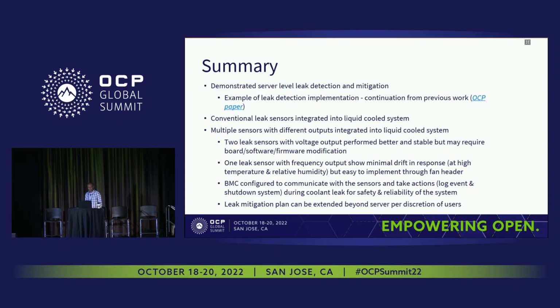To share some of the learnings, the voltage output type sensors seem to perform better. The response is similar, but for aggressive conditions, let's say higher temperature, humidity, and all those conditions, you don't see any kind of drift. We noticed some drift on the frequency-based outputs, just a little drift from the actual specifications provided by the vendor. So that is something to look into on the implementation side.